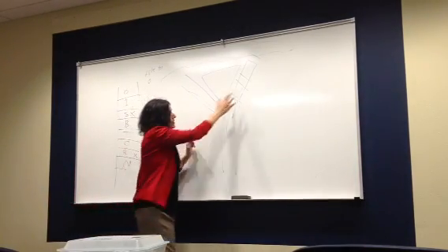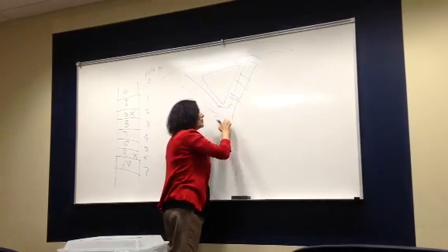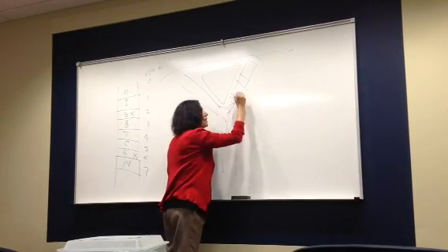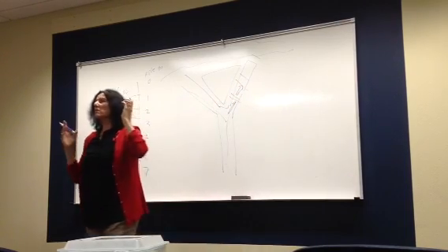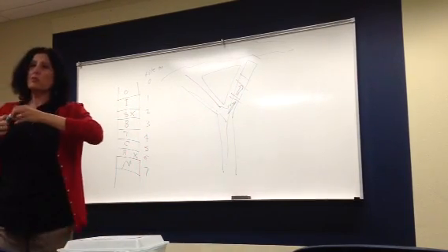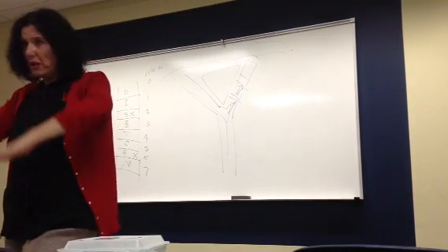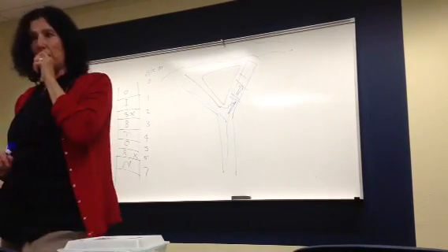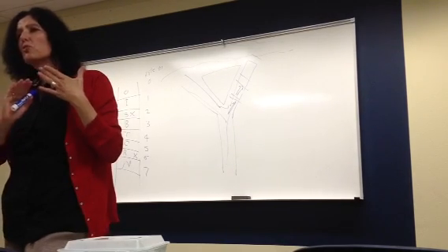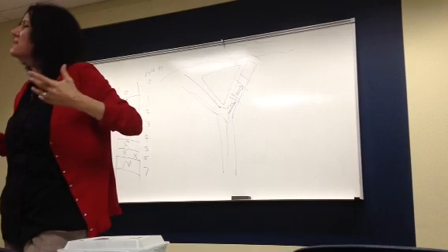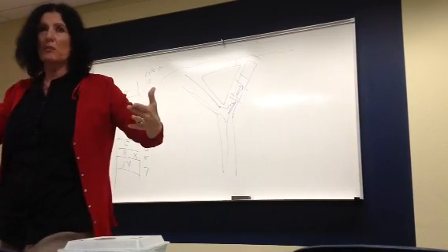Now, for this downstream water, let's assume that I am here, and that's my upstream water, and that's downstream. For this downstream water, the Canadian people did the instrumentation, and they were saying one transmitter to give you the level tank. I said no, at least 3. I cannot in this critical process, and that's as an instrumentation engineer, that's when you come to put your input.